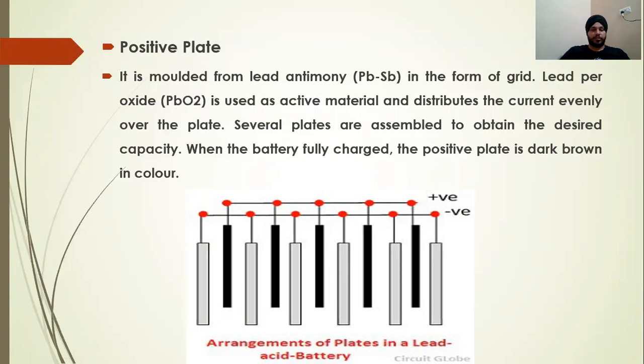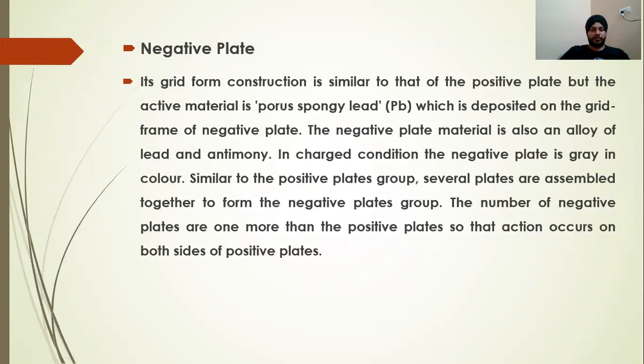Next is the negative plate. It has a grid-form construction similar to that of the positive plate, but the active material is porous spongy lead. The negative plate material is also an alloy of lead and antimony. In the charged condition, the negative plate is grey in color.